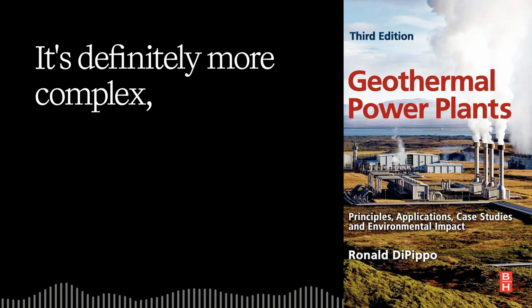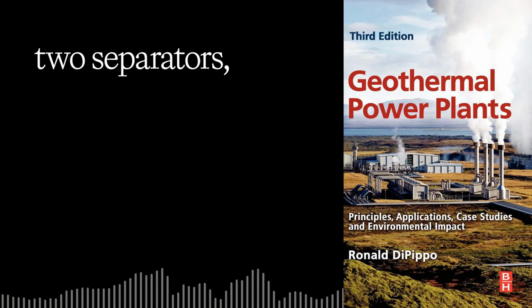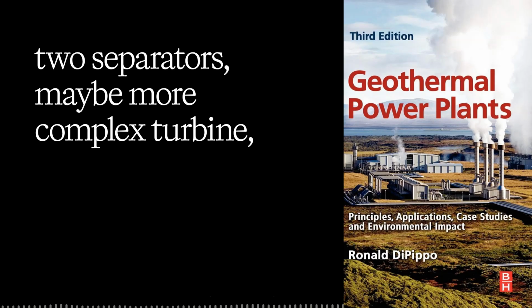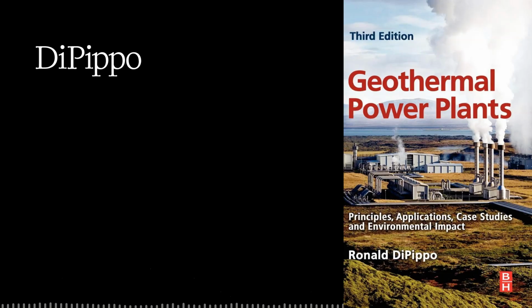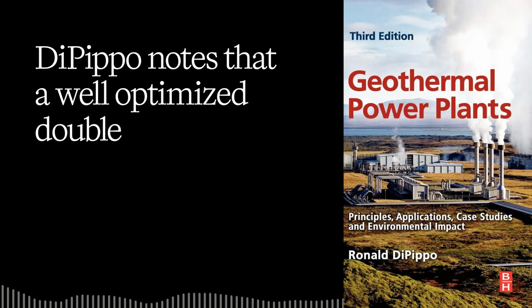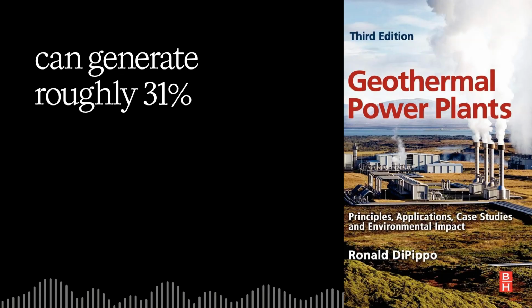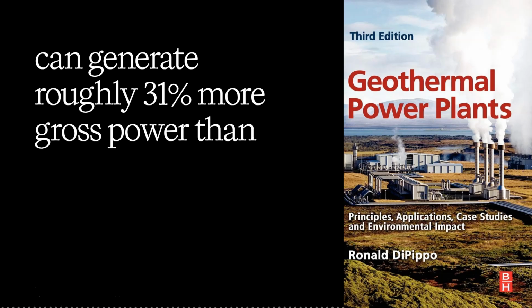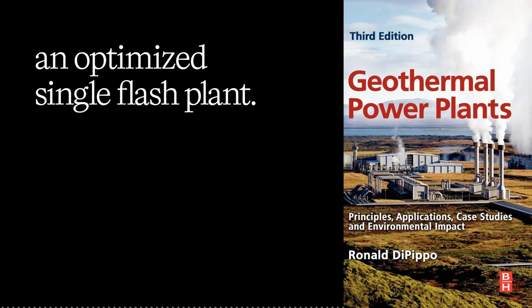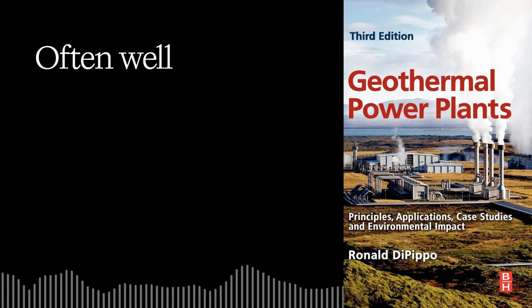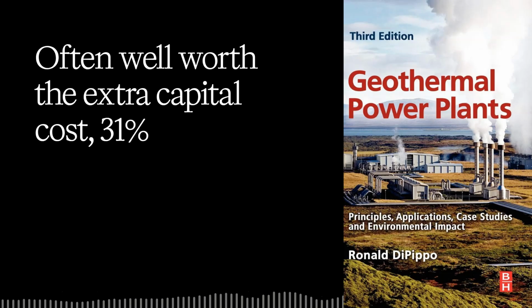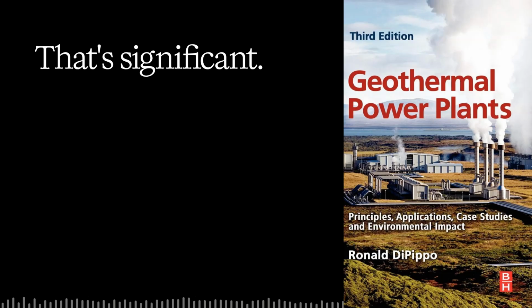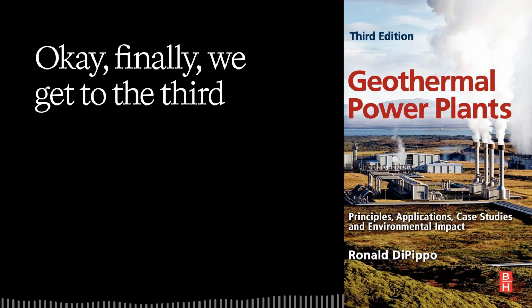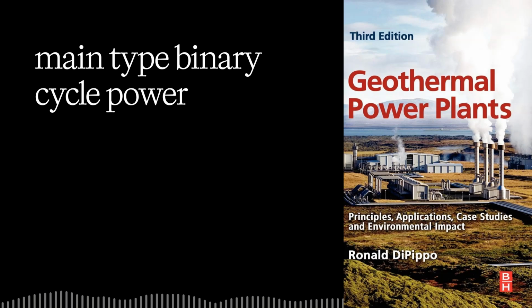It's definitely more complex, requires more equipment, two separators, maybe a more complex turbine. But under the same reservoir conditions, DiPippo notes that a well-optimized double flash plant can generate roughly 31% more gross power than an optimized single flash plant. That's a huge improvement, often well worth the extra capital cost. 31% more power from the same wells. That's significant. Okay, finally we get to the third main type, binary cycle power plants.